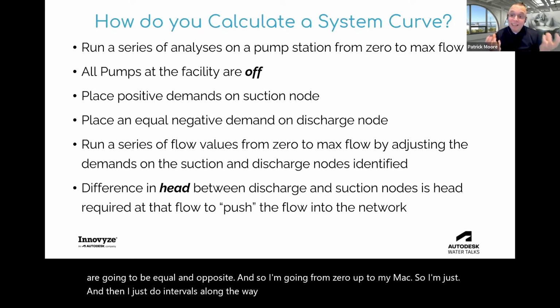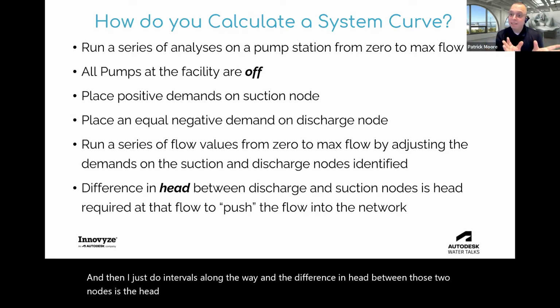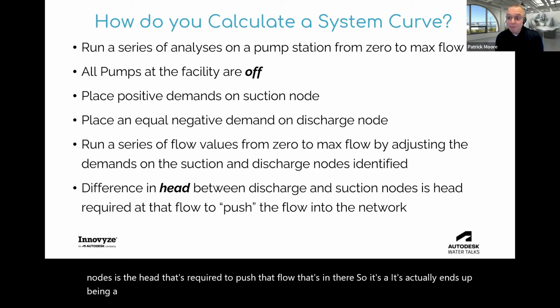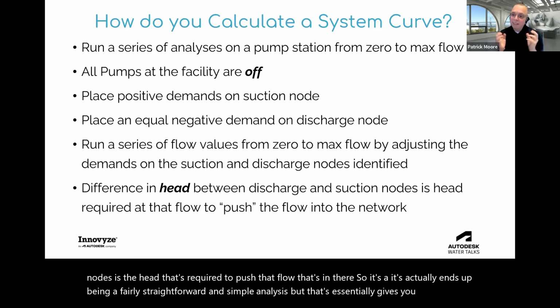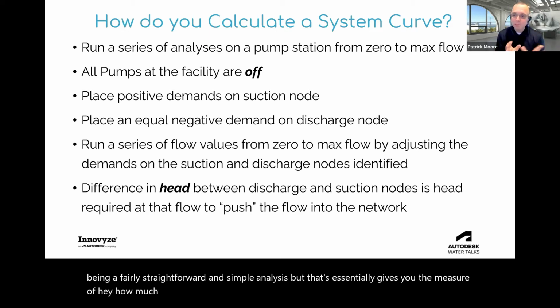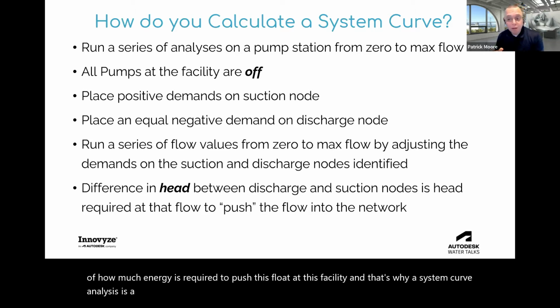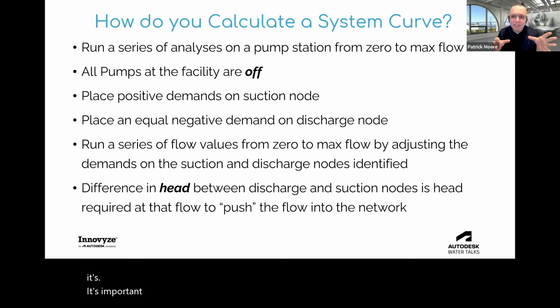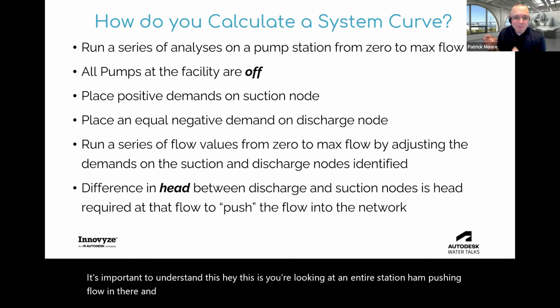And the difference in head between those two nodes is the head that's required to push that flow through. So it ends up being a fairly straightforward and simple analysis, but it essentially gives you the measure of how much energy is required to push this flow at this facility. And that's why a system curve analysis is a station analysis and not a pump analysis. So that's why it's important to understand this: you're looking at an entire station, pushing flow through it.